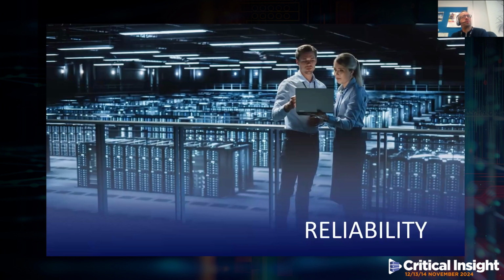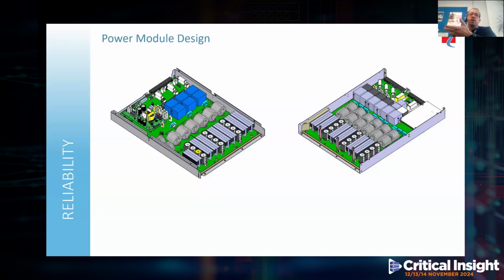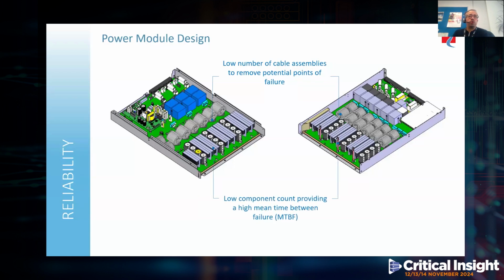Now, one of the key questions about sustainability, and one of the key questions that data center operators want to ask is, does the sustainability come at a cost of reliability? Well, let's take a brief look at the design and the technology implemented to ensure the reliability. Now, the power module, which you can see on the screen there, is constructed with only a few connection cables, which basically removes any potential points of failure. The overall component count is low, which statistically reduces the potential for component breakdown.